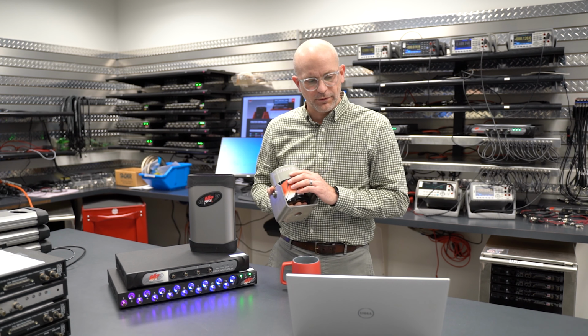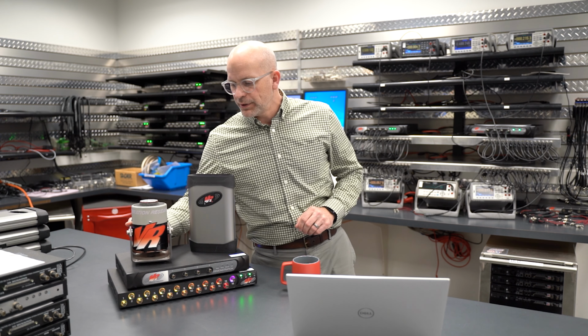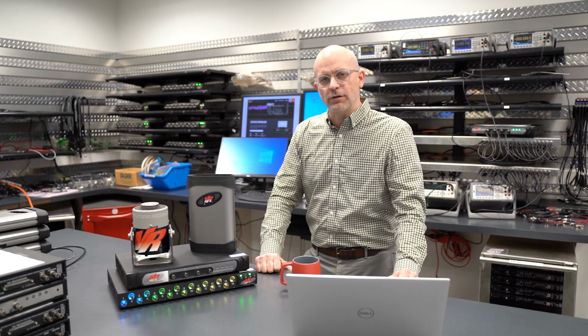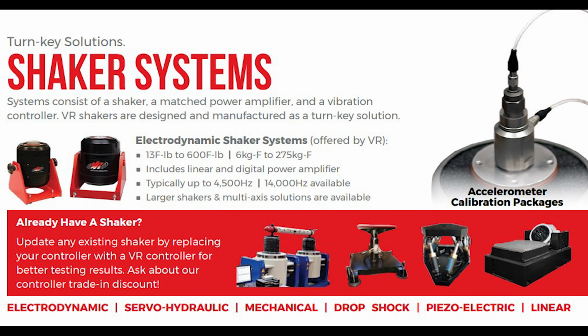We'll be running through some of the specifications on these here in a moment, but the 5200HF is typically used for some modal testing as well as for running accelerometer calibration in a back-to-back application, and we also have that application webinar on our website as well, so you can take a look at how that works. We offer from this size shaker system of 13 force-pounds up to just over a 600 force-pound shaker system. So we'll go through those here in a moment.